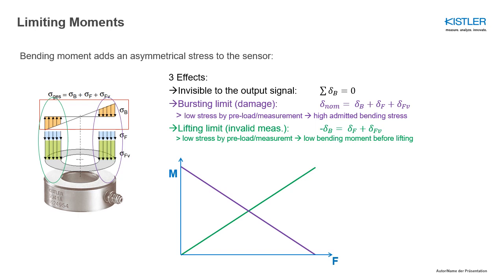What does that mean for our sensor? If you have a look at the graph below, we have two crossed lines. One is the lifting limit, the green one, and the other one is the bursting limit. So we have to stay underneath those two lines with our moment at any time. Of course, this area, this admitted working area, depends on the force that is applied. And if you have a look now where you are allowed to have the highest bending moment, it is at 50% of nominal load. You might remember that we said before, we try to give a preload to the force sensor where we are allowed to operate within this region. And here you can see the reason why.